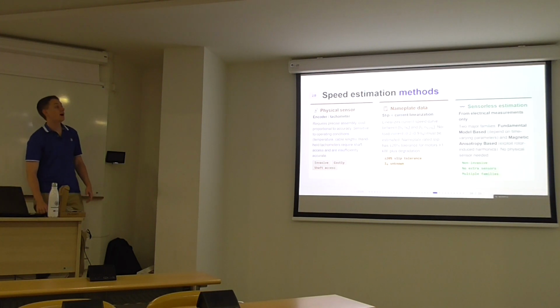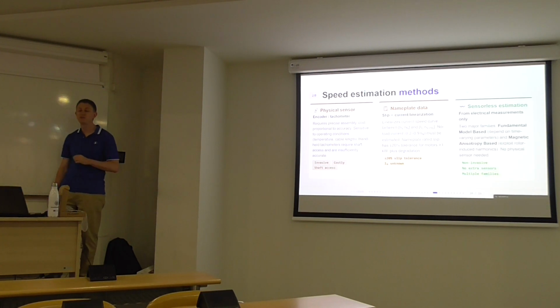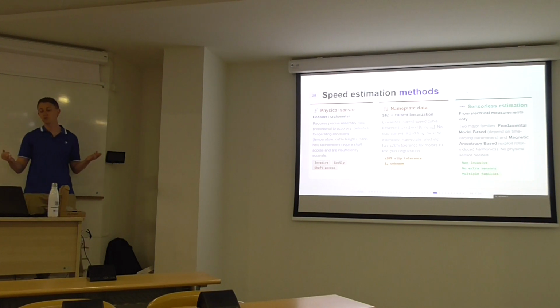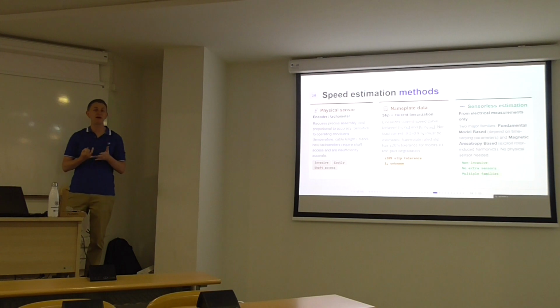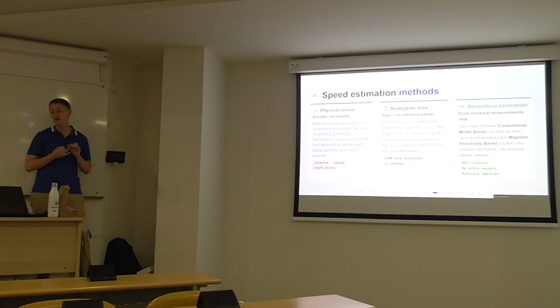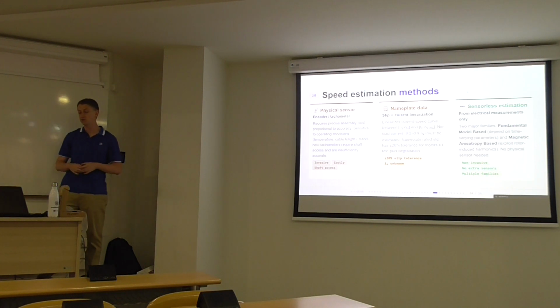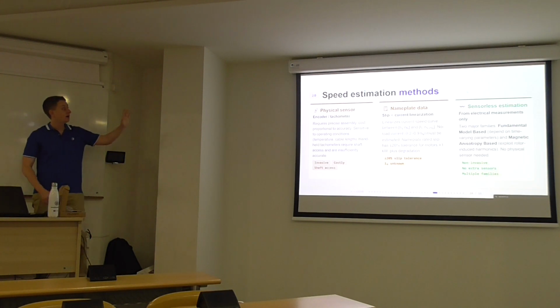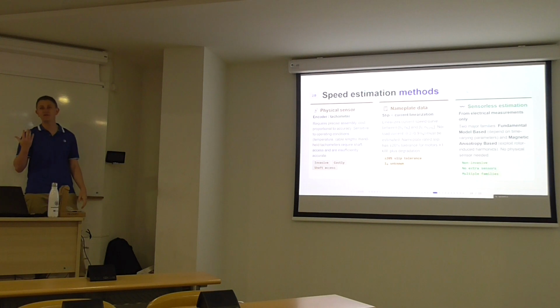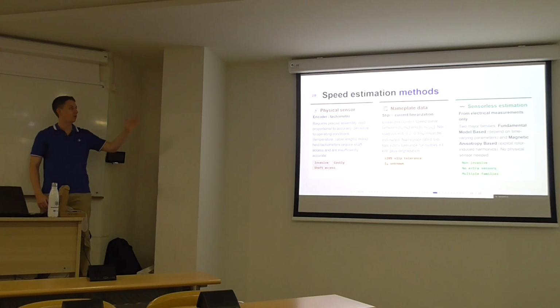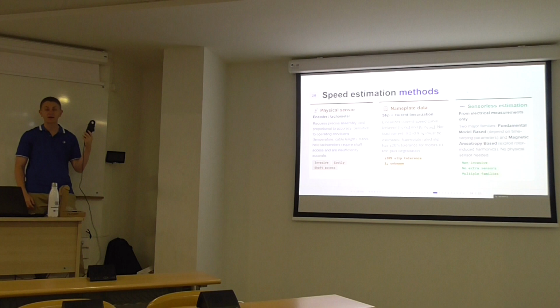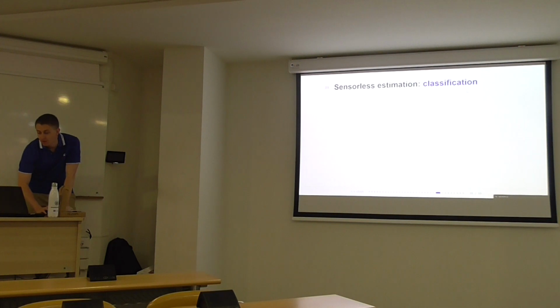And then we have the sensorless estimation from electrical measurements. Here we have 2 groups, okay? Fundamental model-based methods that depend on time-varying parameters, and magnetic anisotropy-based, which exploit rotor-induced harmonics. In this case, we don't require physical sensors, understanding a physical sensor as an encoder or a tachometer. What we need is current clamps, and in some cases, also voltage probes. Okay?